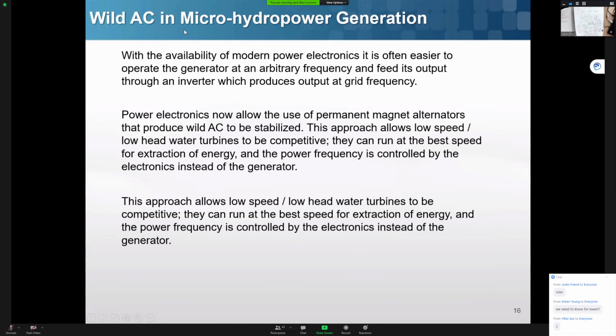Here, in most micro hydro systems, you will just use the rectifier and the inverter, because the micro hydro is not going to have very large power, so you will not use those doubly-fed induction generators in those types of situations.